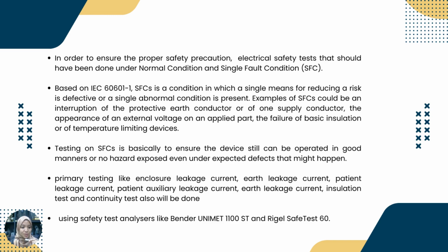In terms of the electrical safety test, we have to put this device through the test in normal condition and single fault condition. Normal condition is to ensure that this device is problem-free and safe to be used. While single fault condition is a test where we make the device become a single fault condition so that we can ensure even if it has any problem, it's still safe to be used and it does not release any hazard to the environment.